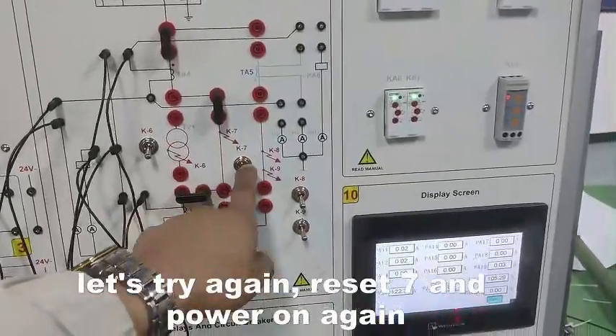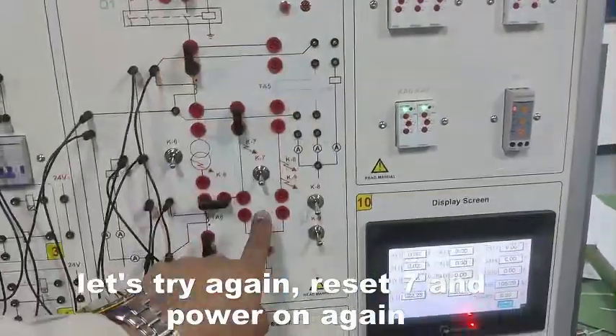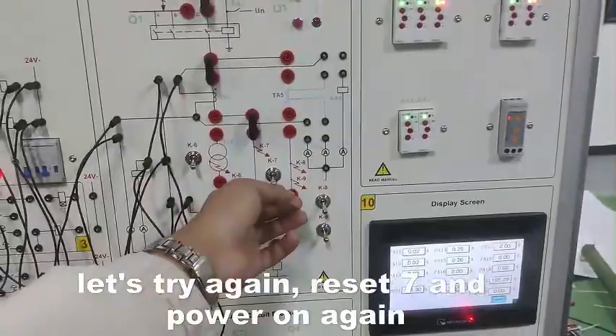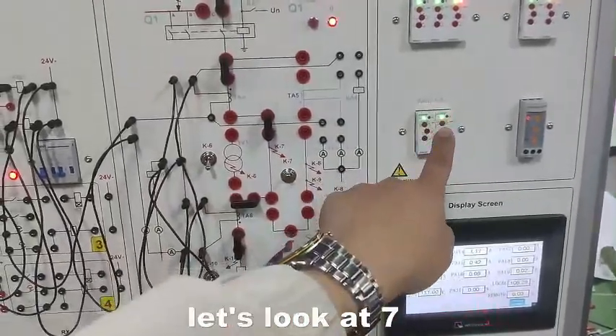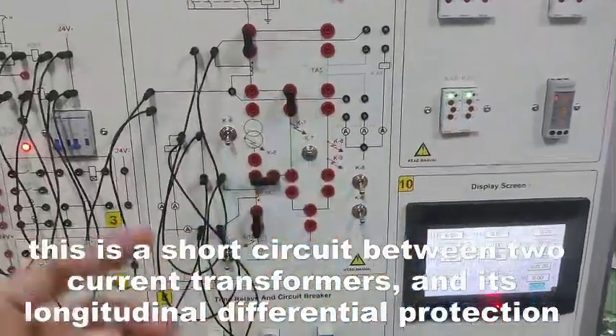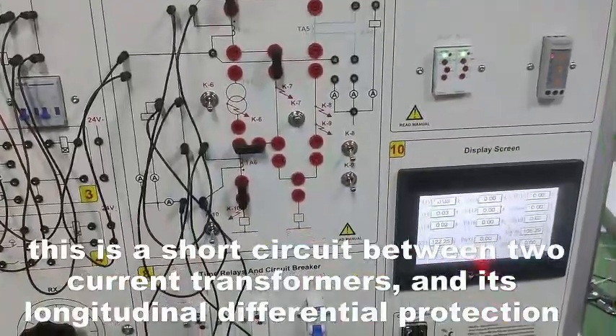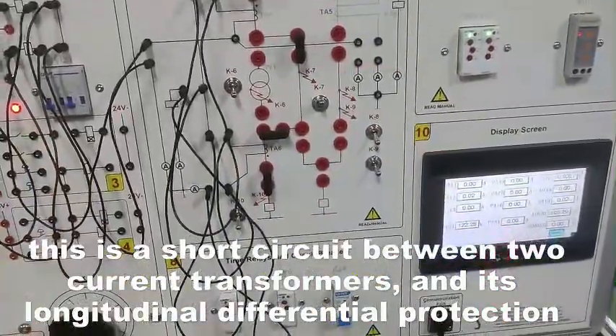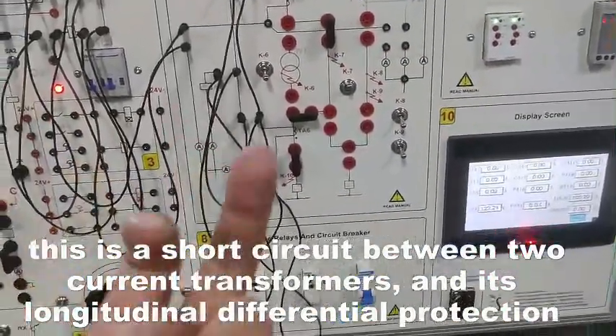Let's try again. Reset 7 and power on again. Let's look at 7. This is a short circuit between 2 current transformers and its longitudinal differential protection.